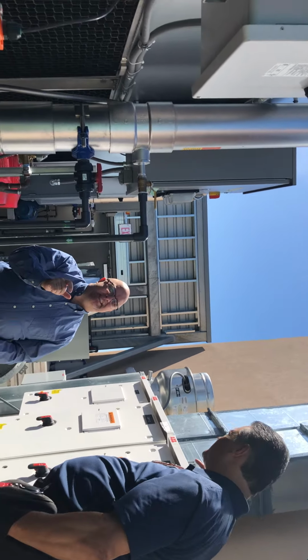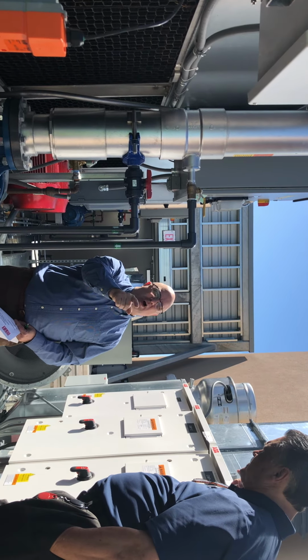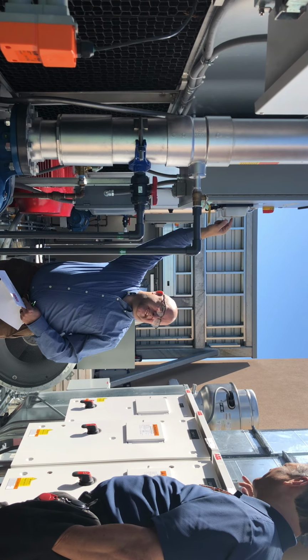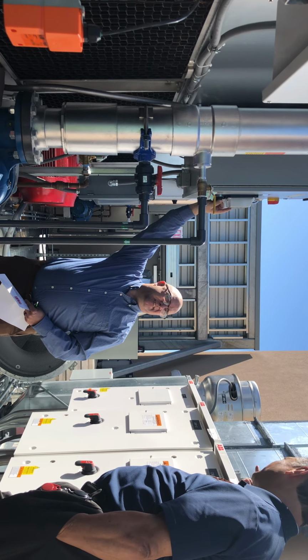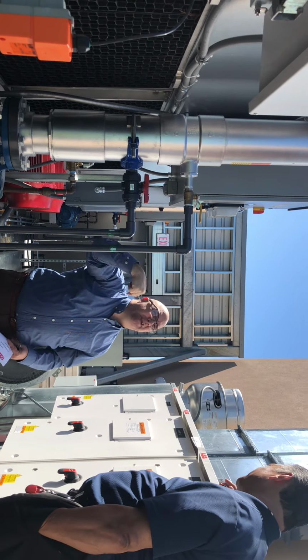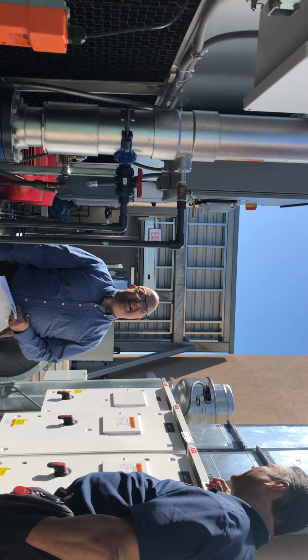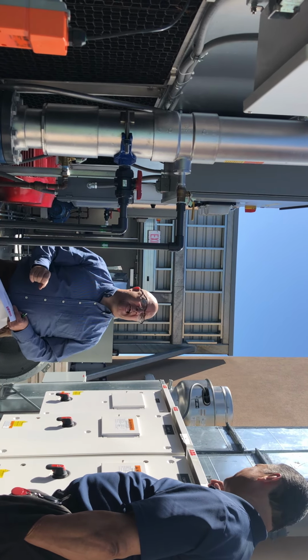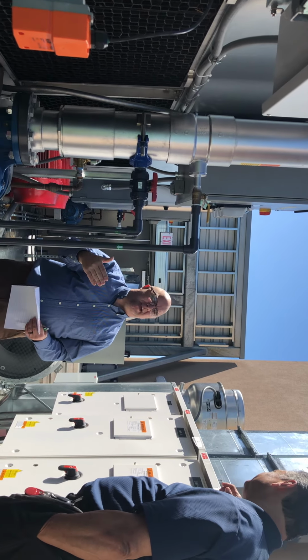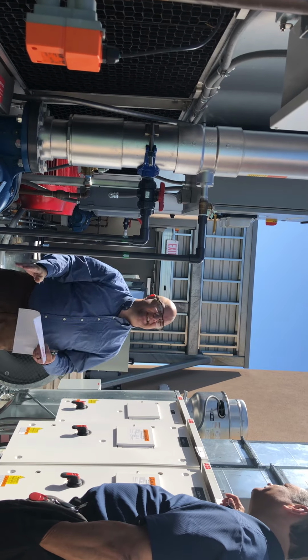I don't actually have the ability to say, now that you're turned on, I want you at 82 degrees. I don't have that ability. It's all dialed in locally here. Which is not on right now, right? Right. Well, it's not turned on right now because I don't need the cooling tower on. It's cool enough outside. The water coming back is not hot. But that's ultimately what's going to happen: as the day warms up or as we get into the warmer months, that water coming back is going to be hot, and these cooling towers will turn on.